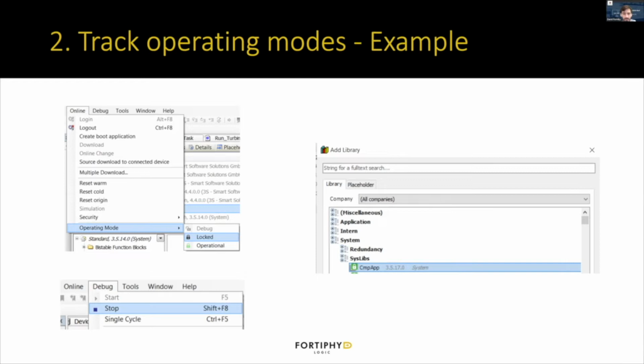So making it operational, it's locked down and doesn't allow changes to the program. There are also different modes between stop and run. So under the debug option in the top menu, you can either stop or start the PLC program. And so that's another way of controlling the mode. And then to monitor that, say you're doing a good job, you're keeping it in the locked or operational operating mode. To monitor that, you first can add the library for CMP app under syslibs under system. So add that library using the library manager.